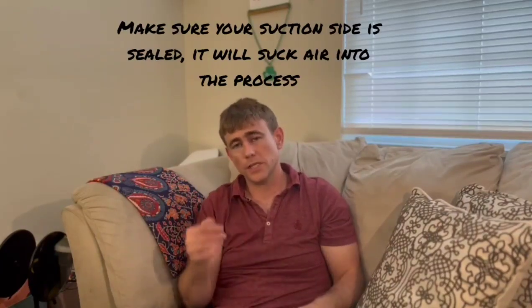And when you're looking at your pressure measurement on a flowing liquid system, there's a couple things that can go wrong. For one, if you have cavitation or any bubbles in your process, you're going to notice that those pressure readings are going to jump all over the place. So if you ever are taking a pressure measurement on a flowing system of liquid and you can't get the readings to stabilize, for me, that's the first place I look. I look at the inlet of the pump and make sure that whatever's going into it is all liquid, and just look around for leaks. That'll make the readings jump around a little bit.